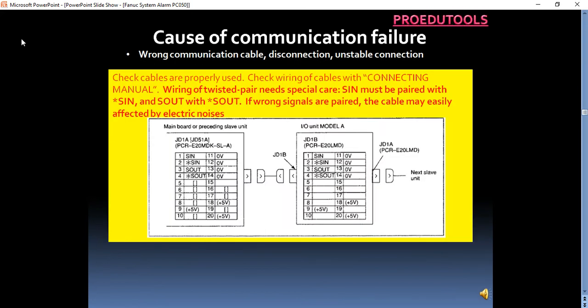Wrong communication cable, disconnection, unstable connection. Check cables are properly used. Check wiring of cables with connecting manual. Wiring of twisted pair needs special care. S-in must be paired with star S-in, and S-out with star S-out. If wrong signals are paired, the cable may easily be affected by electric noises. Do not wire unused terminals. There are power lines such as plus 24 volts and plus 5 volts, and unintended wiring of these lines may cause malfunction of devices.